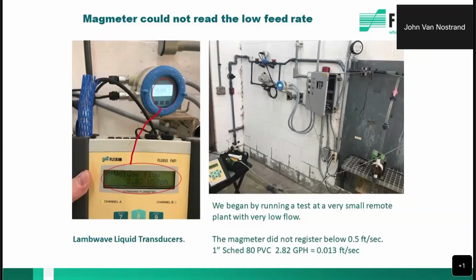In this particular case, a customer installed a magnetic flow meter to ensure the proper dosing of sodium hypochlorite. The magnetic flow meter didn't stand a chance during off-peak times because the flow was so low. I mean, look at this system here. They've got, it looks like, one Stenner pump moving sodium hypochlorite through a 1-inch line, and take a look at what that flow meter says, 0 flow. But in actuality, there was 2.8 gallons per hour, which is 0.013 feet per second. No chance a Magmeter is going to read that.